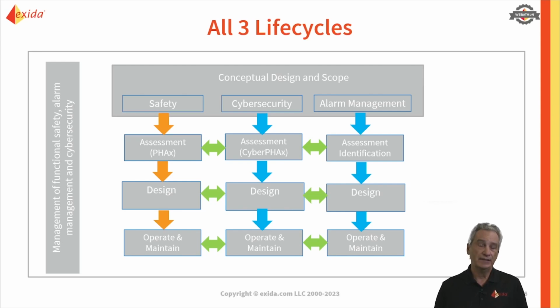And interestingly, from the functional safety point of view, with the change made to IEC 61511 in 2016, they added in a clause for cybersecurity, which is 8.2.4, which requires us to do a risk assessment on the safety instrumented system. So this is something that we need to do now. And that of course ties in with the standard pointing us towards following the 62443.